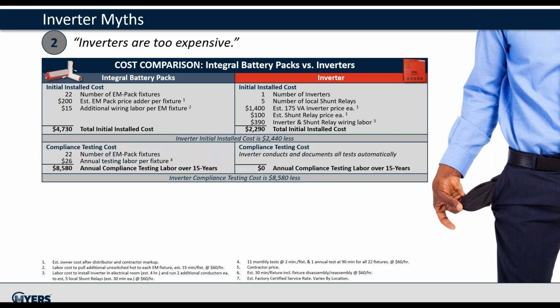Now that the system is installed, it must be maintained through the required compliance testing. For integral battery packs, a test time of 2 minutes was assessed per fixture per month, and 90 minutes for all 22 fixtures once per year. At $60 per hour labor rate, the total compliance testing for 15 years is $8,580. The inverter already has the code-compliant monthly test and yearly tests performed automatically.